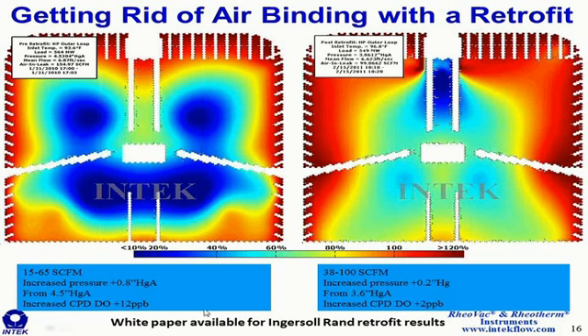However, with the retrofit installed on the right-hand side, if you take a look at the blue box at the bottom, in that bundle, the air in leakage was increased from 38 to 100 SCFM. The back pressure only increased 0.2. And the condensate pump discharge measure of dissolved oxygen only increased 2 parts per billion. So not only is this bundle more immune in terms of being resistant to condenser pressure rise, but it's also more immune to air in leakage because of less condensate dissolved gases. Again, there's a white paper on this retrofit at the same location on our website.